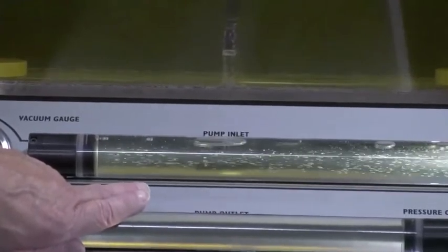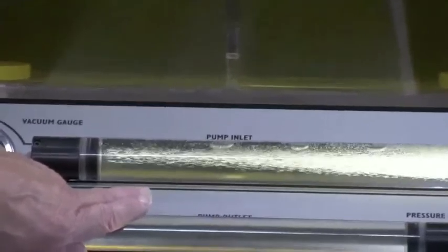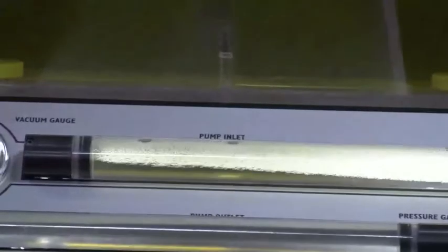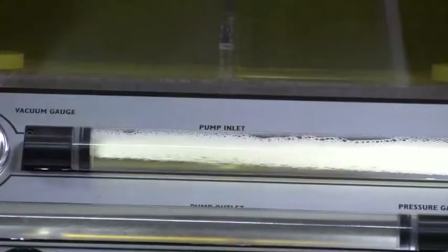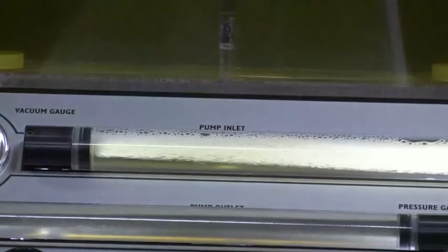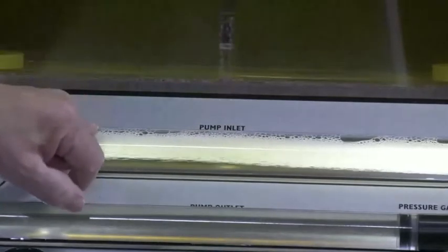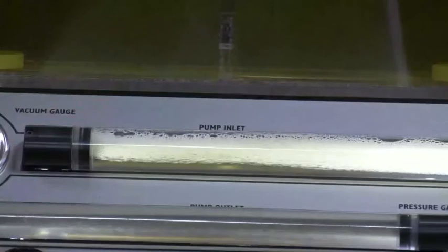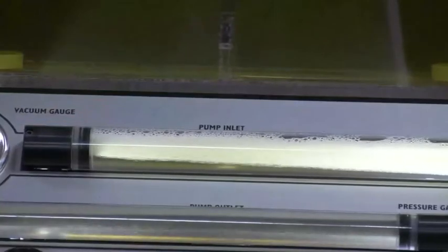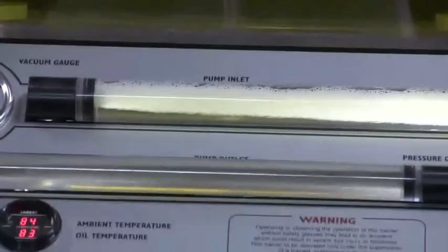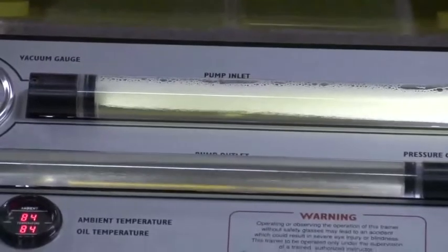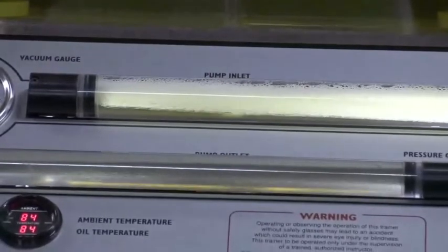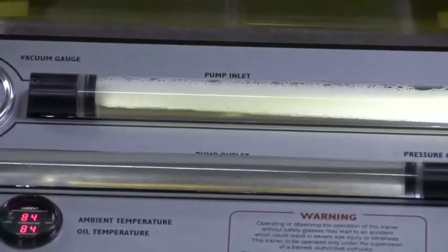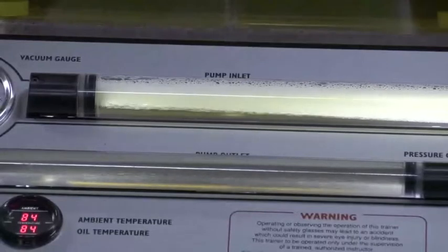There it comes. I'm in full-blown cavitation right now. Dissolved air out of the liquid. This is cavitation, the formation at the intake and collapse on the discharge side of the pump of gaseous cavities within the liquid. My inlet restriction is way up there. I've taken it well over 15 inches of mercury just to make the point. But that, my friends, is full-blown cavitation.